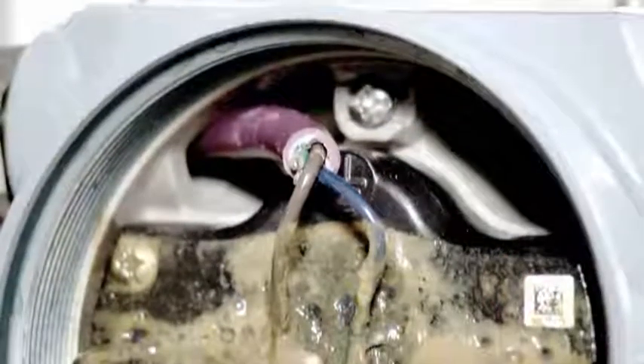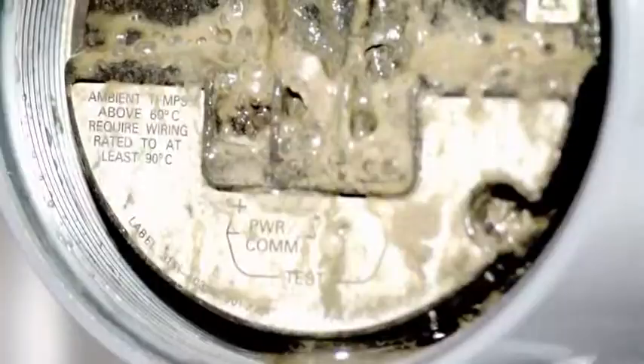Corrosion can occur inside a junction box or on the transmitter terminals, and when this happens, the wiring resistance of the loop changes. The analog value that is being read by the system may be different from the actual process value, and without diagnostic detection of this failure mode, your safety system will be prevented from responding to unsafe process conditions.